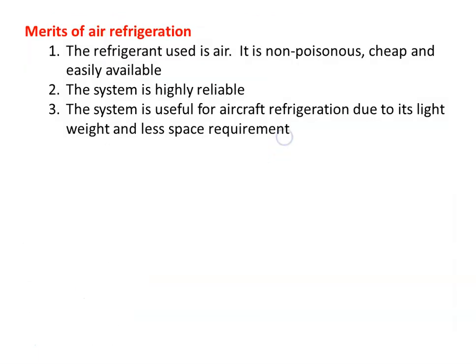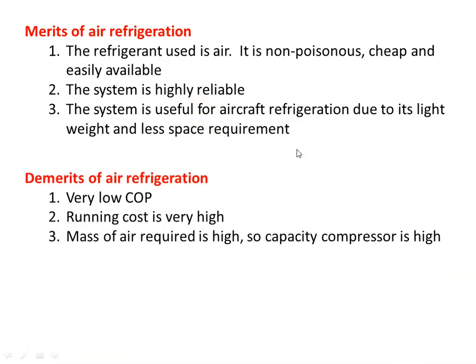The advantages of air refrigeration: the refrigerant used is air — non-poisonous, cheap, and easily available; the system is highly reliable; and it is useful for aircraft refrigeration due to its light weight and small space. The demerits are very low COP and high running cost, because bigger equipment is required — bigger capacity compressor and evaporator. This system is used only for aircraft refrigeration, not for commercial or industrial refrigeration.